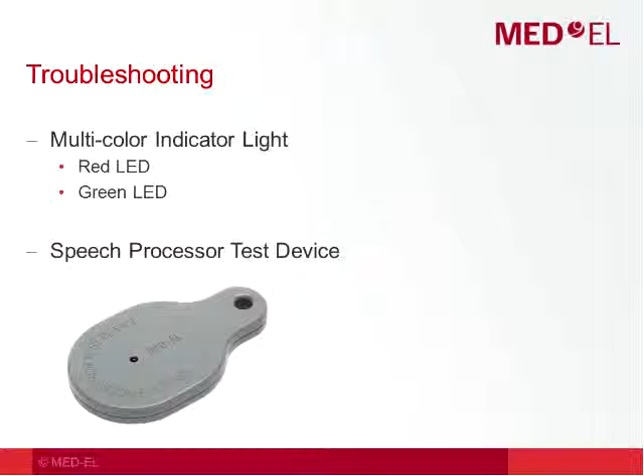We also have a little sound check device that we call a speech processor test device. So as long as those lights are telling you that everything is good, then you can use this speech processor test device to double check that the cable and the coil are okay as well. Like I said, those cables just kind of break sometimes. So I often recommend that you just kind of use this device every morning when you turn your equipment on to make sure that that cable is still good before you get going on your day.